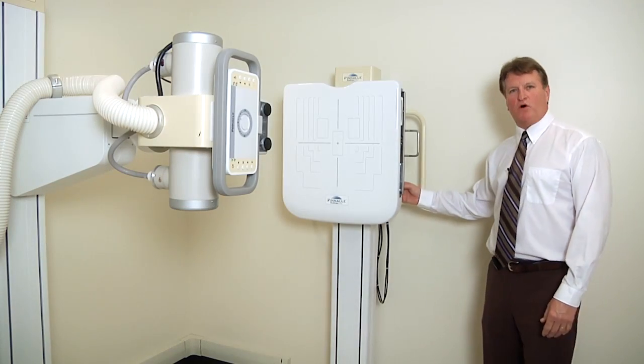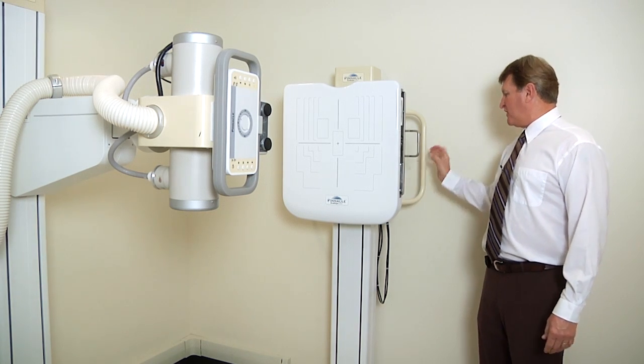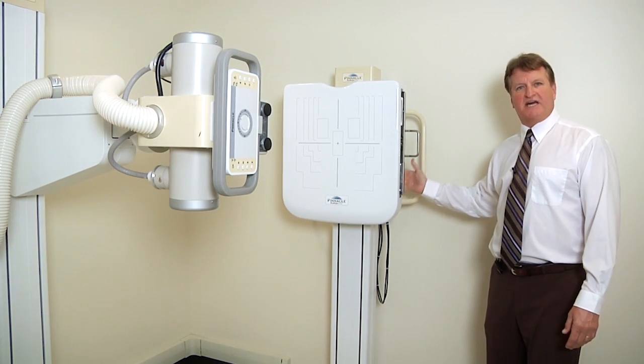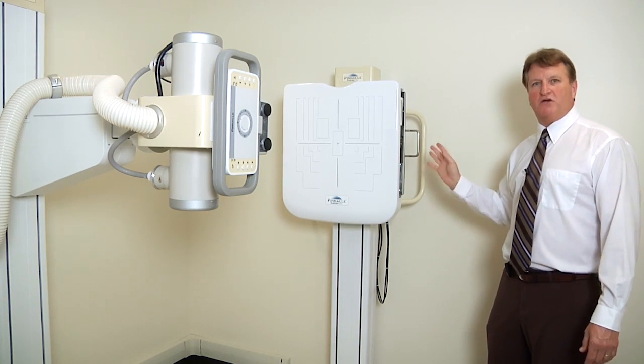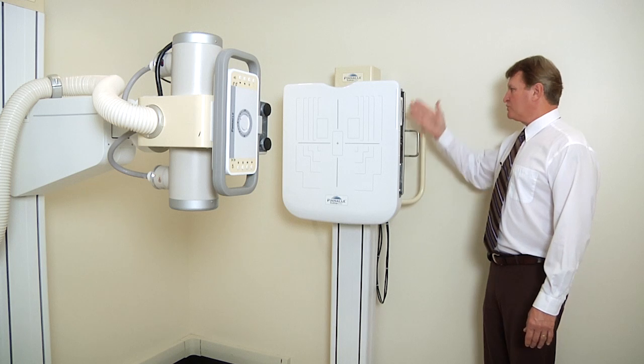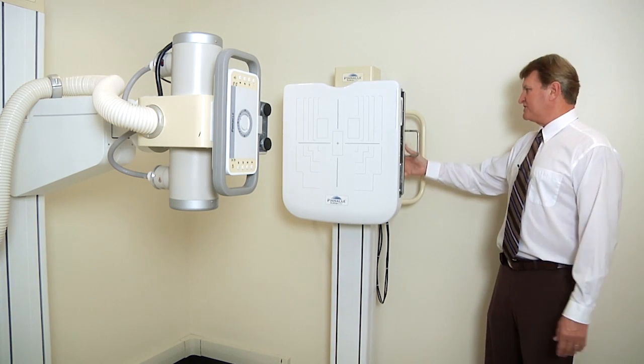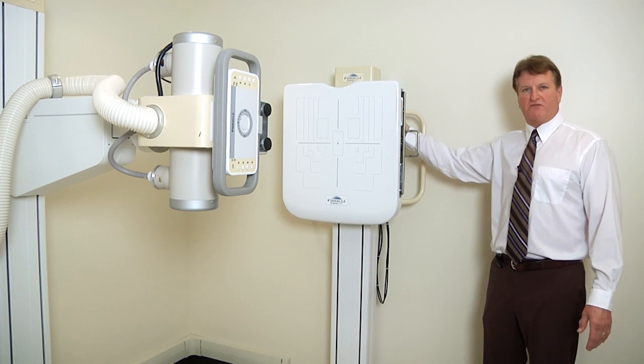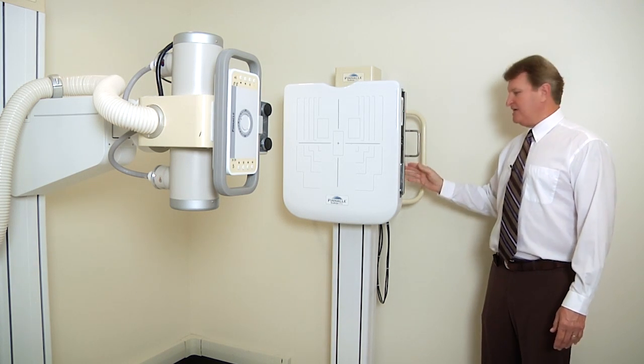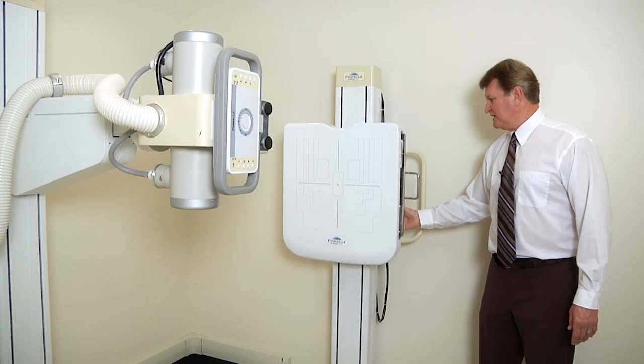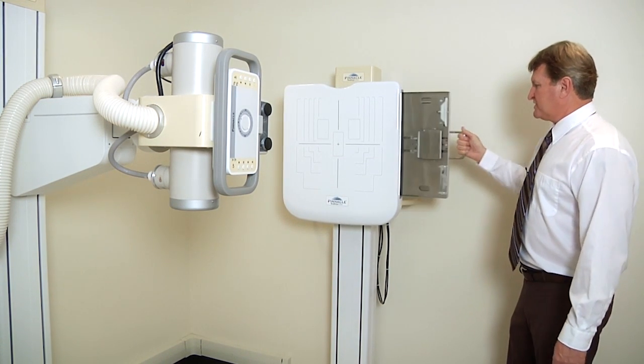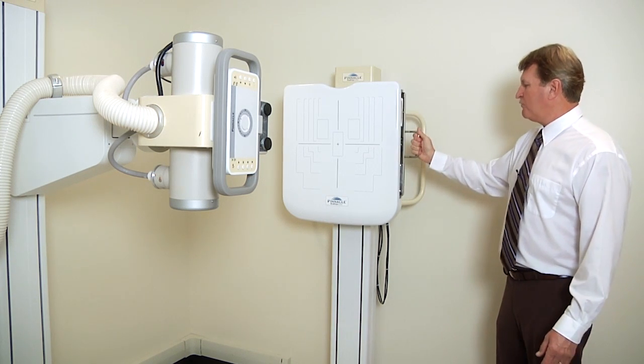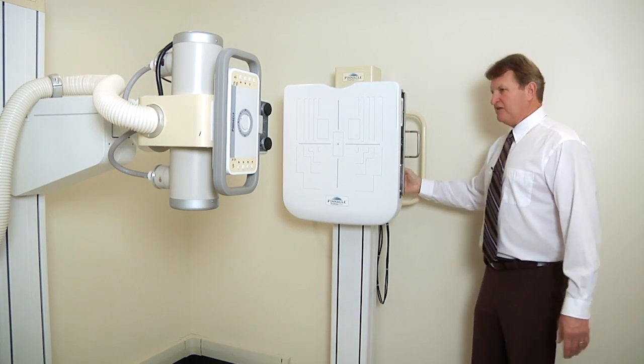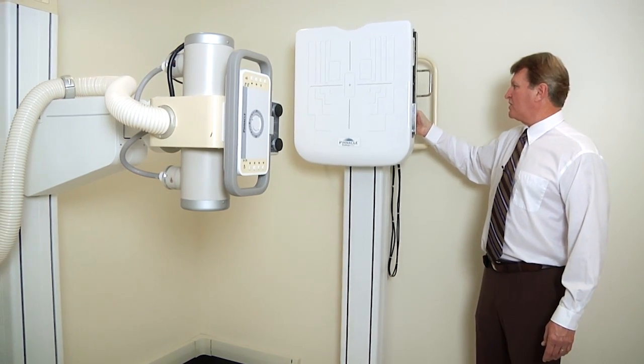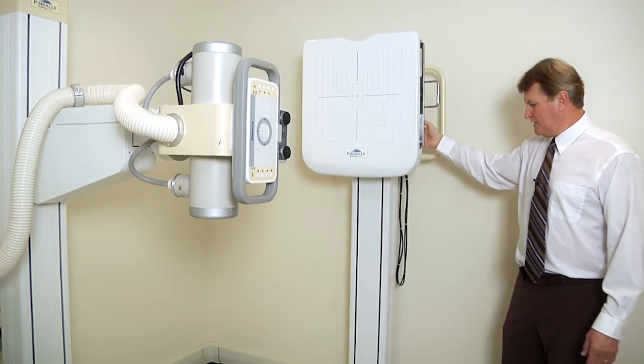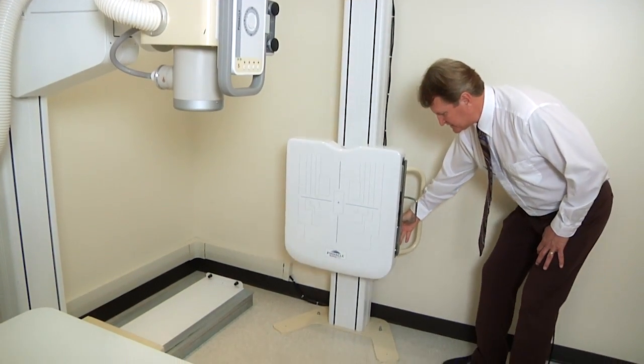Our exclusively designed wall stand includes hand grips on either side and lock release on either side. It's very easy to convert from a right-hand load to a left-hand load in the field. There's a tremendous amount of vertical movement due to the design, and also since the counterweighting is done in the front part of the cabinet instead of in the column, it allows it to be a very smooth moving system. We use the same cassette tray in the table and in the wall stand with the positive lock. The vertical movement allows tall C-spine imaging to be done, as well as standing knees.